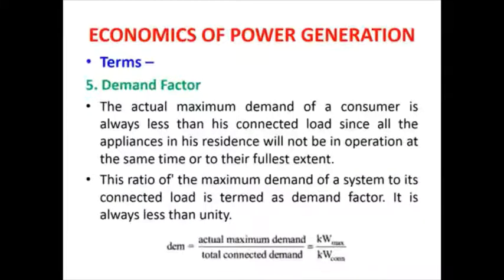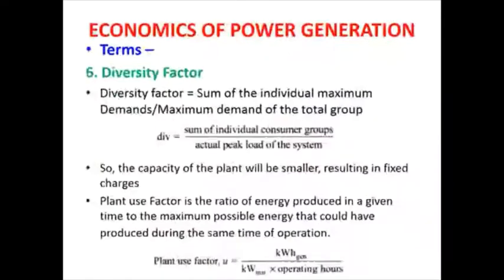So the ratio of maximum demand of a system to its connected load is termed as demand factor. So it is always less than unity. It is equal to actual maximum demand divided by total connected demand.